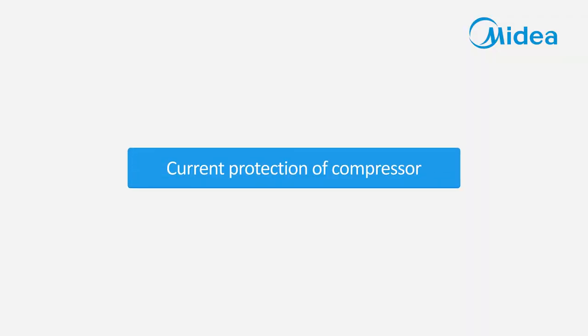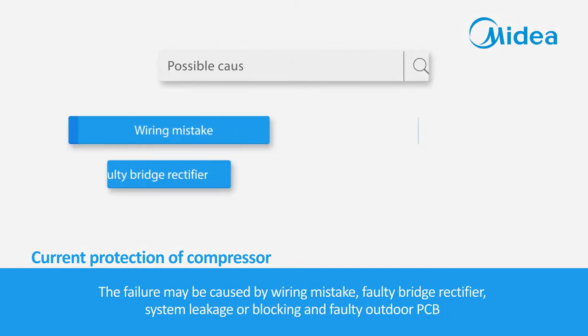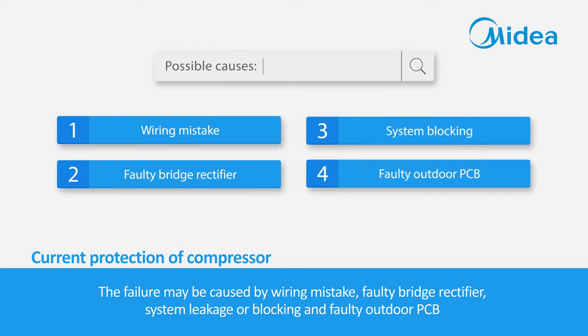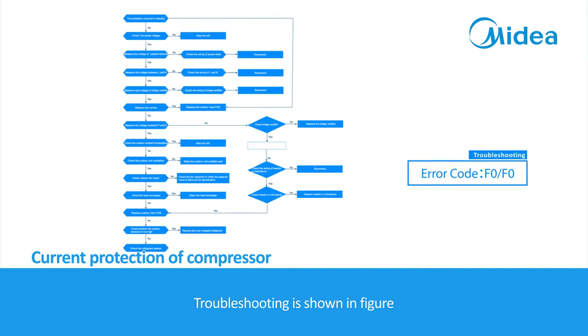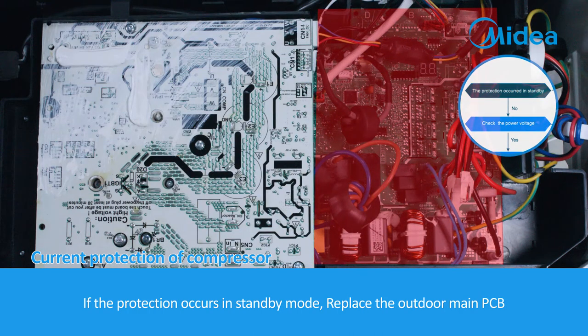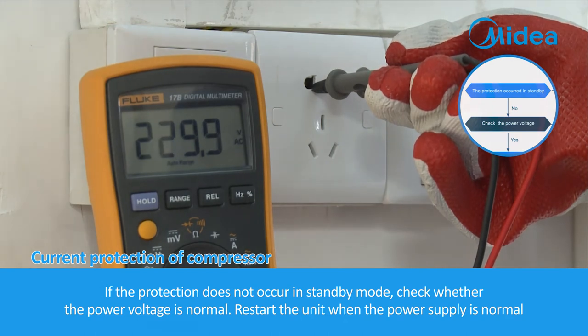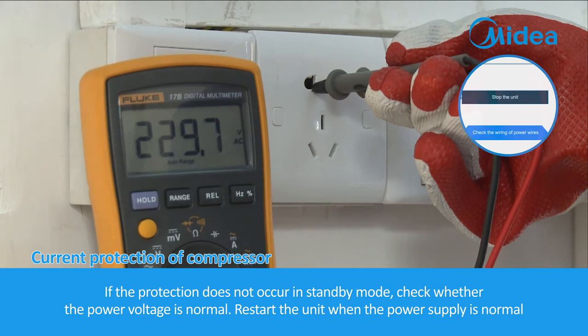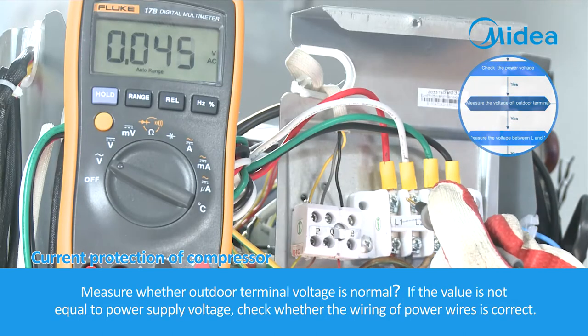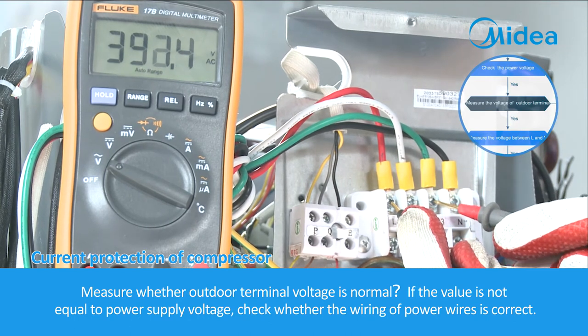Current protection of compressor. Malfunction conditions: if the outdoor current exceeds the current limit value, the LED will display the failure. The failure may be caused by wiring mistake, faulty bridge rectifier, system leakage or blocking, or faulty outdoor PCB. Troubleshooting: if the protection occurs in standby mode, replace the outdoor main PCB. If the protection does not occur in standby mode, check whether the power voltage is normal and restart the unit when the power supply is normal. Measure whether the outdoor terminal voltage is normal; if not equal to power supply voltage, check the wiring of power wires.